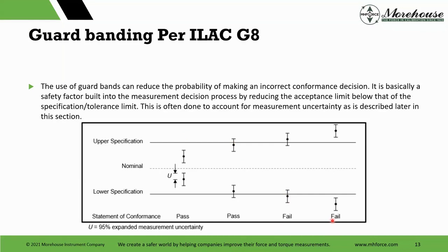So conformity assessment, like I like to say, is not black and white when we take the measurement uncertainty into account and everything's inside the specification limits versus some things outside. So when we say 2% risk, what we're saying is only 2% of this is going to hang out. And from this picture, more than 2% is hanging out. So we get into an indeterminate situation where this is a pass for sure, right? This, per the new ILAC G8, is a conditional pass. You may report this. I'm not a big fan of it because I think we need to report the appropriate level of risk. This is a conditional fail. It still may be good, and this is a fail, which we'll see a picture later to the points of all of this.